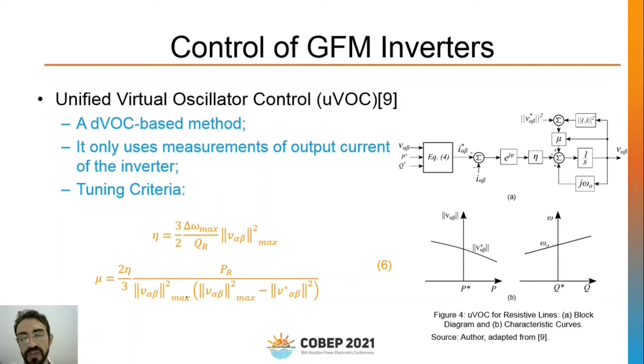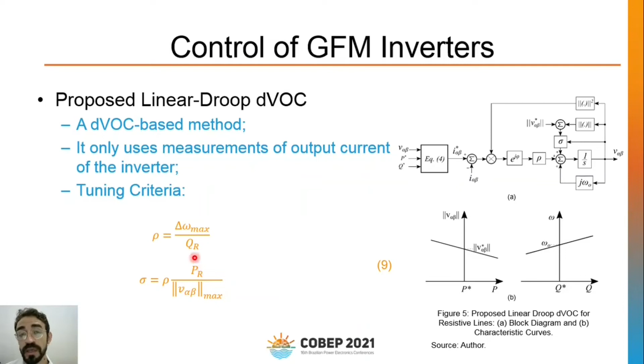In this work, we propose a new dispatchable virtual oscillator control, which also only uses output current as a measurement for the control, and has the following control law. It has the same structure as that of unified virtual oscillator control. The sigma gain is related to the voltage error, and the rho gain is related to the error of output current. A very important point of this control is its linear droop relationship, which has a behavior closer to conventional droop control, and brings the advantage of a simpler tuning criteria, defining the rho gain as the ratio between maximum deviation of frequency and rated reactive power, and the sigma gain is related to maximum voltage deviation and rated active power.